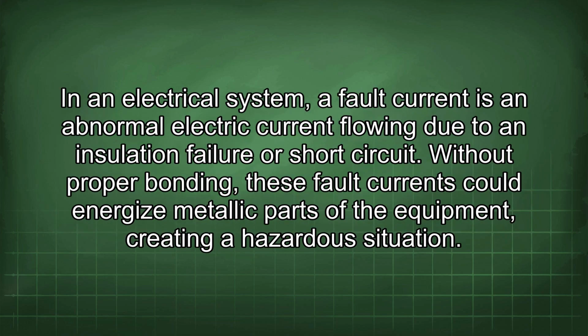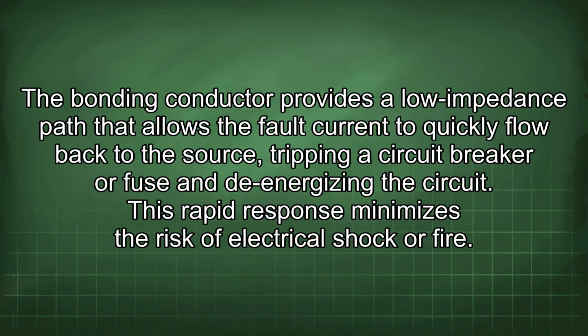In an electrical system, a fault current is an abnormal electric current flowing due to an insulation failure or short circuit. Without proper bonding, these fault currents could energize metallic parts of the equipment, creating a hazardous situation. The bonding conductor provides a low impedance path that allows the fault current to quickly flow back to the source, tripping a circuit breaker or fuse and de-energizing the circuit. This rapid response minimizes the risk of electrical shock or fire.